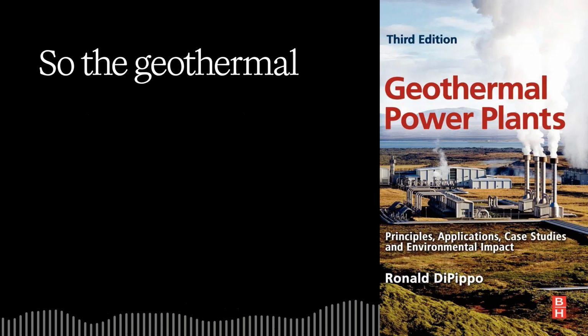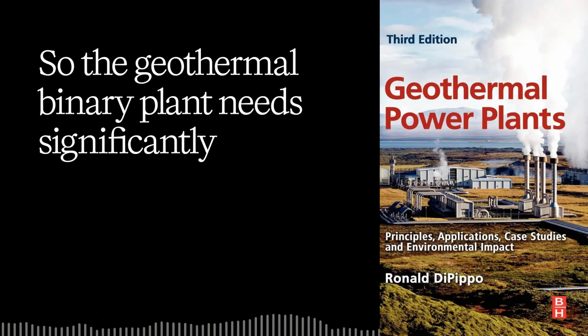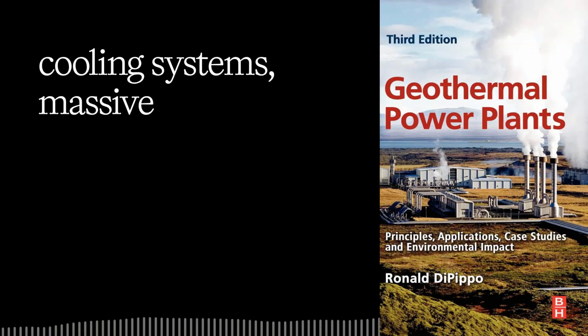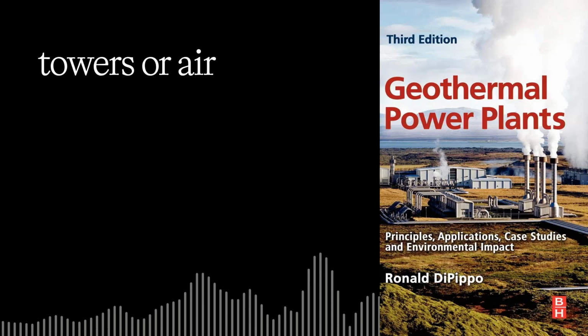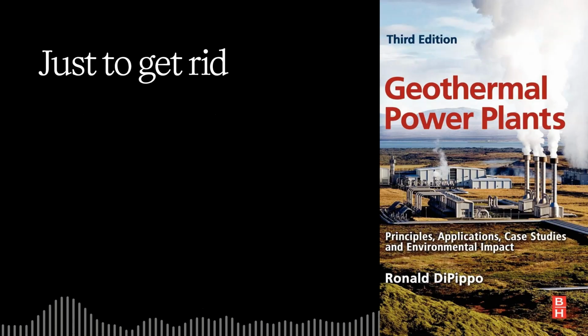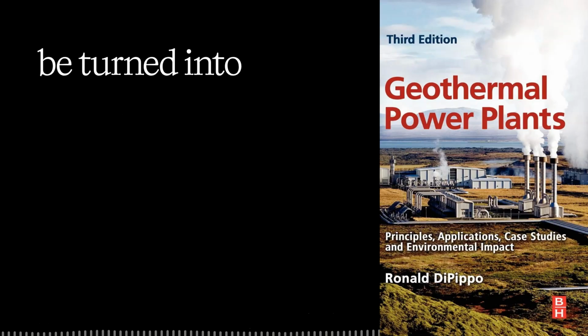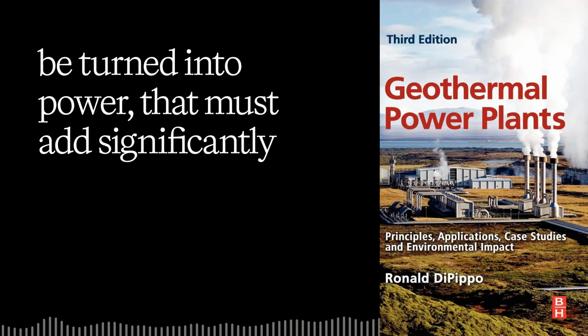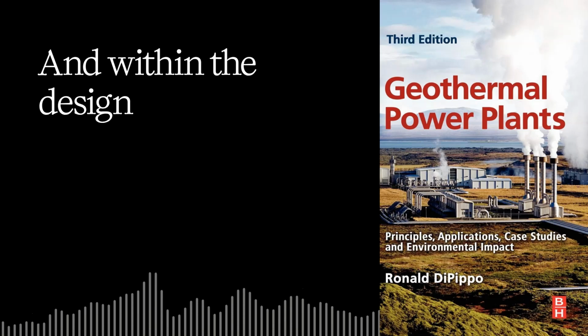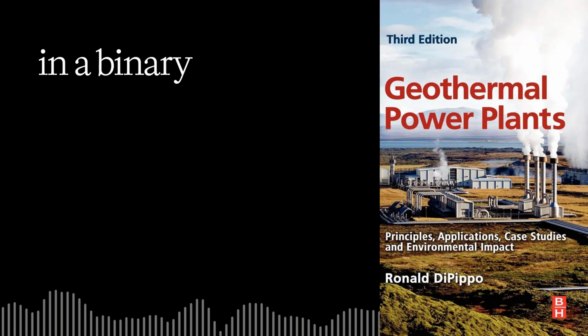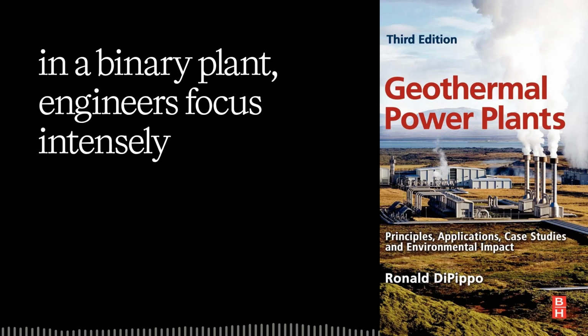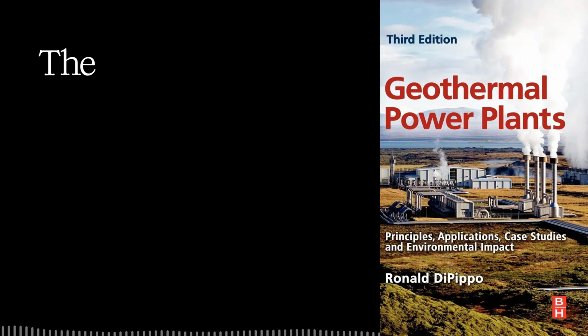So the geothermal binary plant needs significantly larger cooling systems, massive cooling towers or air-cooled condensers, just to get rid of all that low-grade heat that couldn't be turned into power. That must add significantly to the plant's footprint and cost. Absolutely. And within the design of that critical heat exchanger in a binary plant, engineers focus intensely on something called the pinch point. The pinch point, what's that?